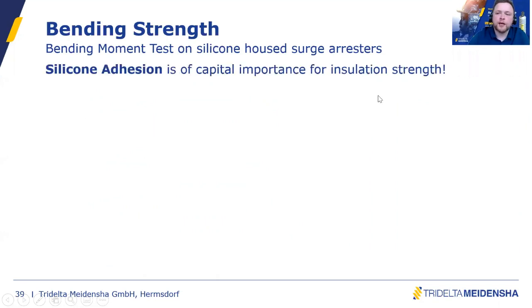One thing we have to test as well is the silicone adhesion. This is an integral part of the bending test. And of course, silicone adhesion plays a capital role for the insulation strength of the surge arrestor. If there is no adhesion, water can ingress, and water will definitely produce a conductive path and will lead to a breakdown of the surge arrestor very early.